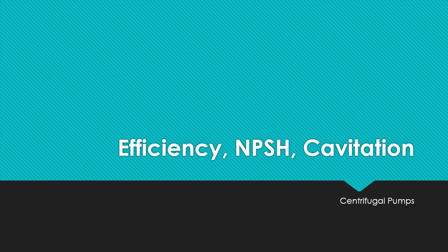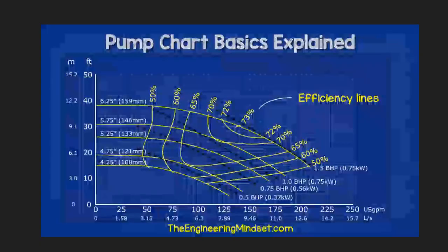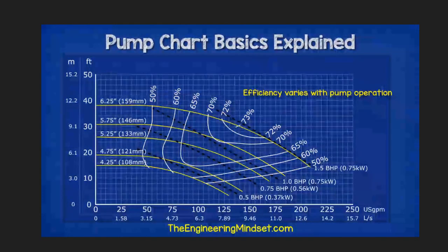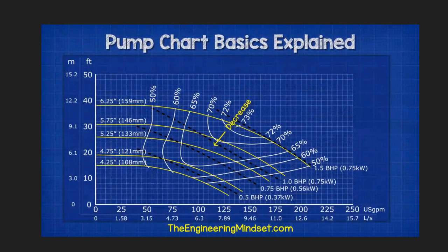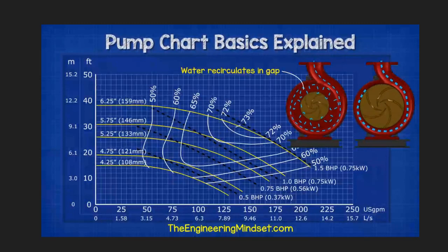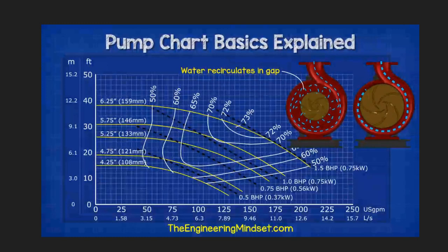We will be discussing efficiency, net positive suction head, cavitation, and centrifugal pumps in these slides. The chart will usually have efficiency displayed in more complex plot lines, where each line displays the percentage of efficiency. In multiple impeller size charts, efficiency decreases as impeller size decreases, because the gap between the impeller and the pump casing increases, allowing water to recirculate in that region and waste energy.